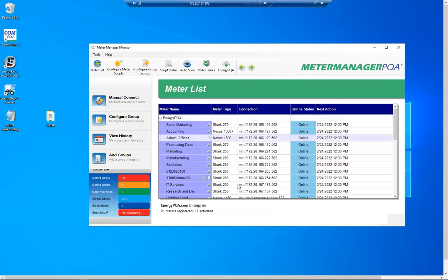So if you want to do that, your best option is, when you configure the system, either do it on individual groups. For new meters, if you only have one new meter, go into the one new meter, right-click test it. In general, you don't need to retest meters that have been working for 6 months. If the CTs are wired backwards, they're wired backwards. They're not going to unwire themselves.